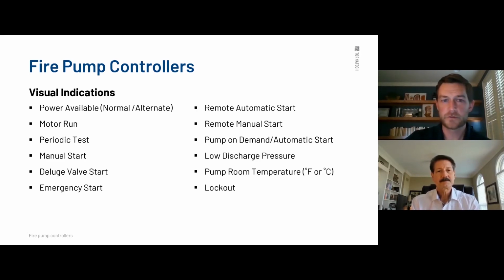If it's a deluge, it'll say deluge. For emergency start, it says EMER. I think it might say emergency all the way out, but EMERG. So whatever your starting method is, it'll tell you on the screen. Plus, it'll log it that way as well. Remote automatic start, remote manual start, pump on demand, low discharge pressure, pump room temperature. That's not required, but we do that. Pump room temperature, that's up on the top right. And then lockout.